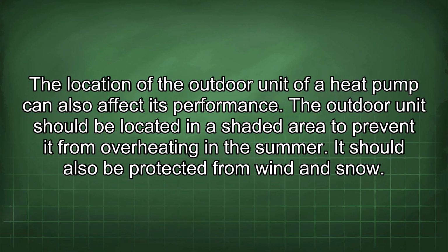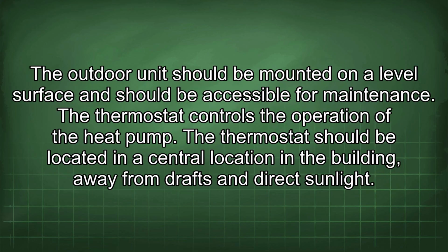The location of the outdoor unit of a heat pump can also affect its performance. The outdoor unit should be located in a shaded area to prevent it from overheating in the summer. It should also be protected from wind and snow. The outdoor unit should be mounted on a level surface and should be accessible for maintenance.